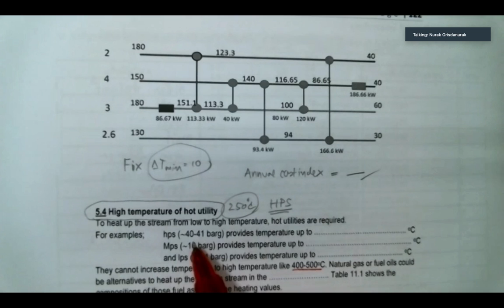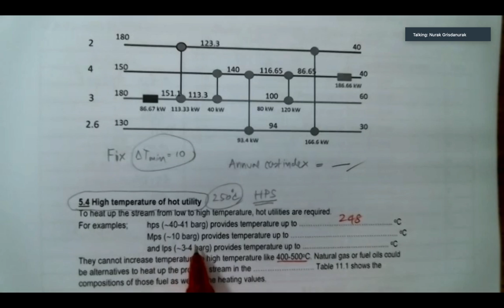Now let's talk about if I have high pressure here at 41 bar gauge, you will reach this temperature in Celsius. And if you go for 10 bar gauge of medium pressure steam, the temperature will hit only 184 degrees Celsius. And the medium low pressure steam of 4 bar gauge, you can go up to only 160 degrees Celsius.